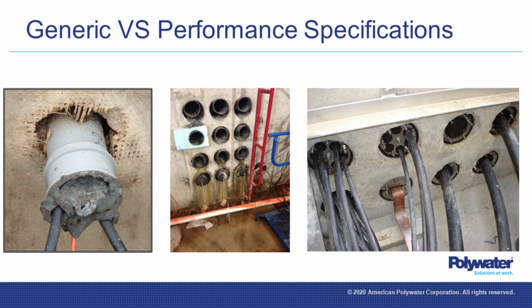All right, so remember I told you that the industry standard is to use a 0.35 coefficient of friction. That's their multiplier. But they use that 0.35 no matter what kind of cable you're pulling in, meaning the jacket, whether it's PVC, cross-linked polyethylene, or low-density polyethylene, and whatever conduit you're pulling into. There is no one coefficient of friction. So for example, let's say you've got a conduit that's got a lot of water in it, or it's an older conduit system.